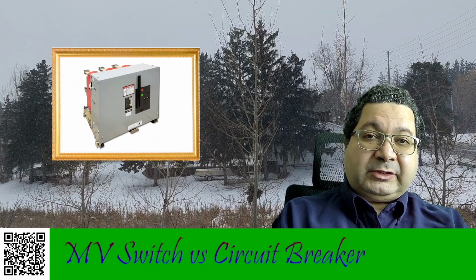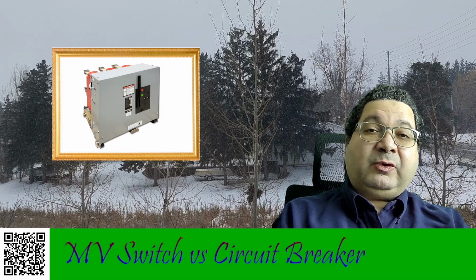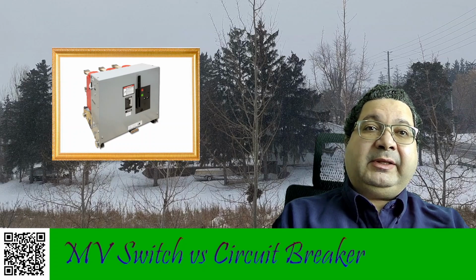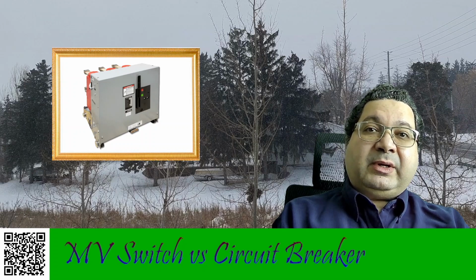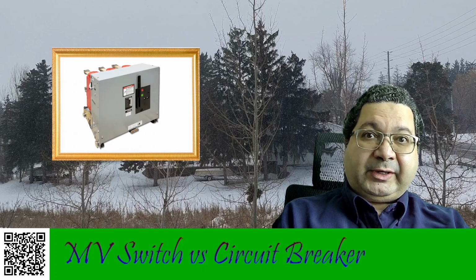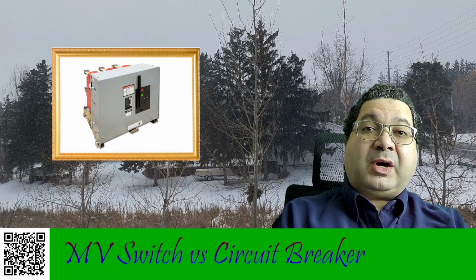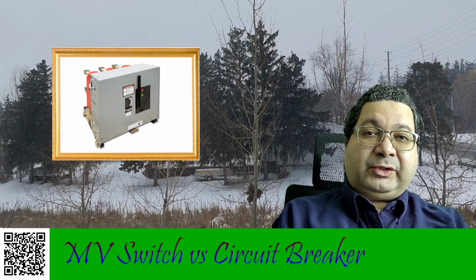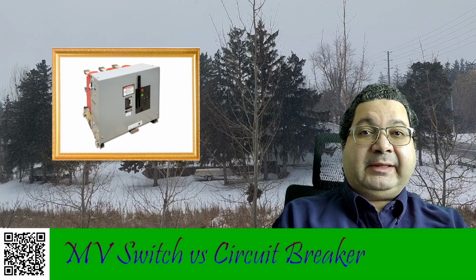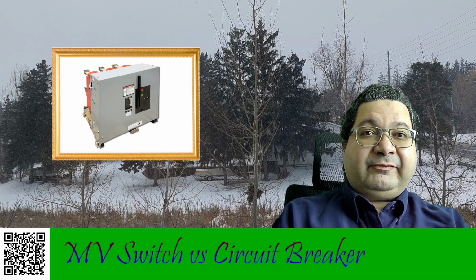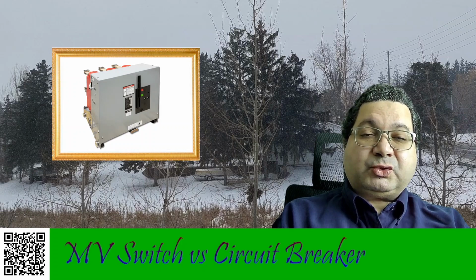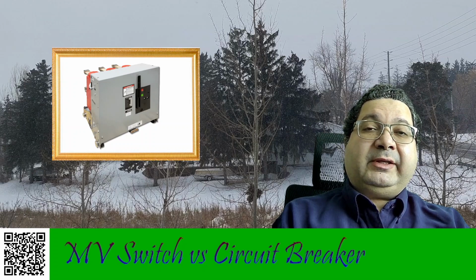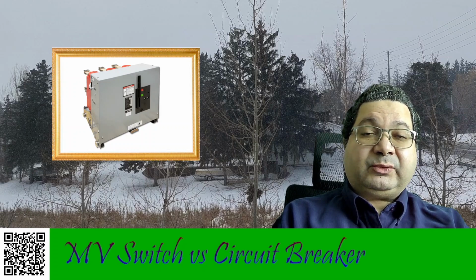However, for a breaker, typically it is 10,000 mechanical operations, which means it can open and close without load, and probably one tenth of that, which is 1,000 times of electrical operation. And of course, it can also interrupt an arc. So you can open a breaker during an arc, and it also has interrupting capacity for the short circuit level. That's why the breaker is very important in our network.